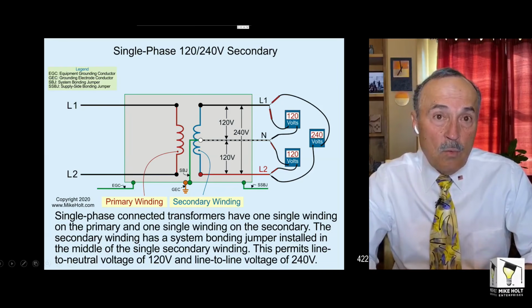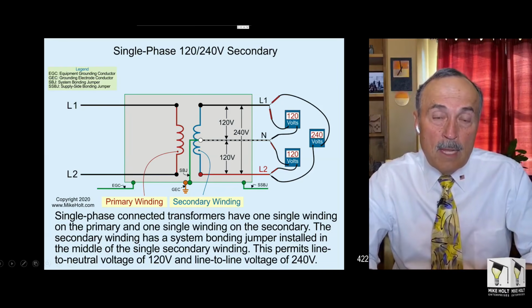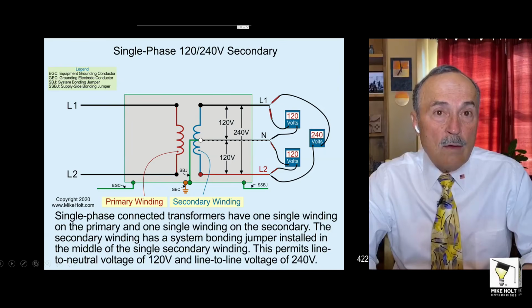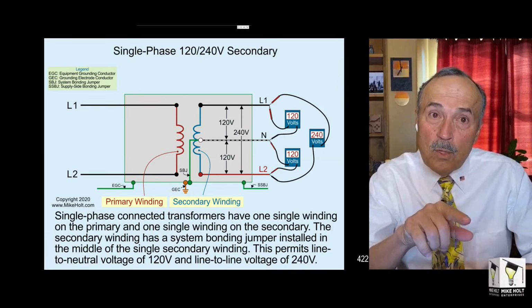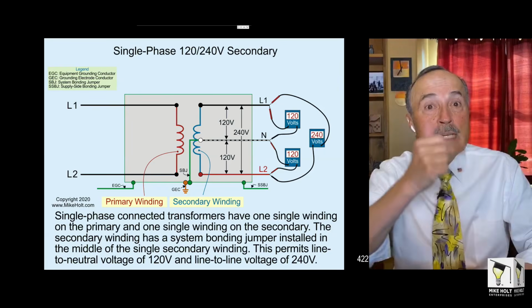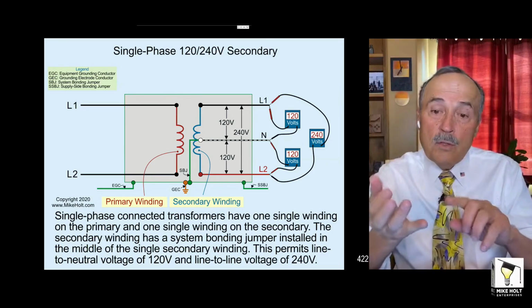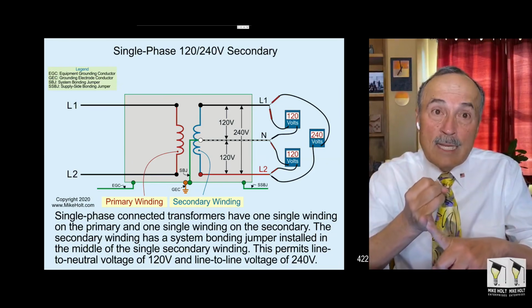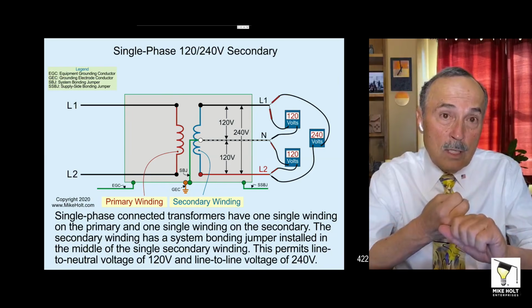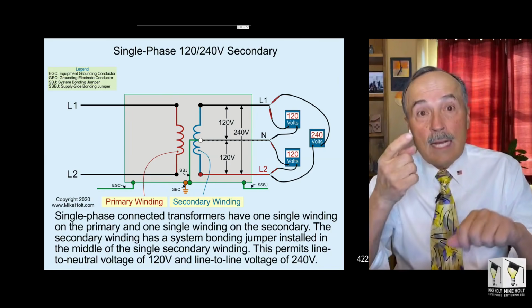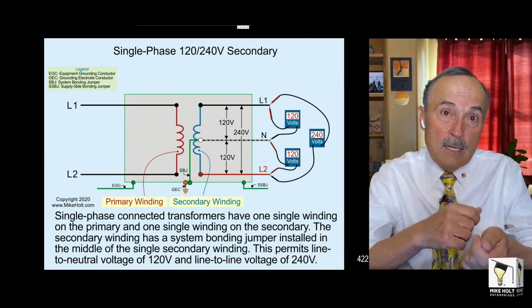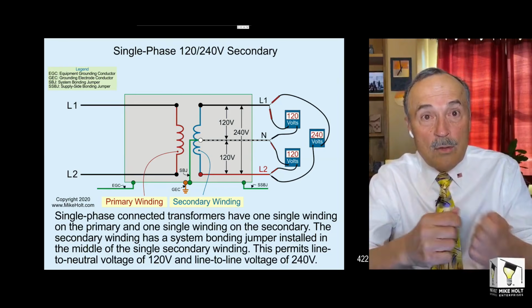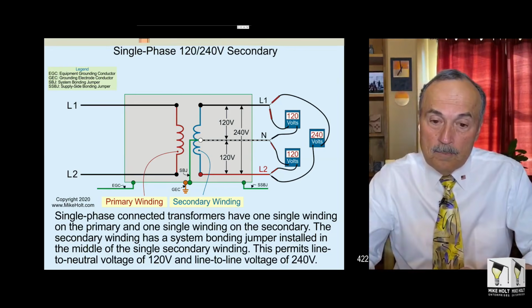You take the secondary winding, which is a separately derived system, and we're going to bond it to the case. Then we're going to take both the case and that X0 terminal, and we're going to ground it to the earth, either at the point of the separately derived system or the first disconnecting means afterwards. But wherever you do the system bonding jumper, that is where you have to do the grounding electrode conductor. Or wherever you do the grounding electrode conductor, that's where you have to do the system bonding jumper. But it can be either one of those two locations in a transformer here.